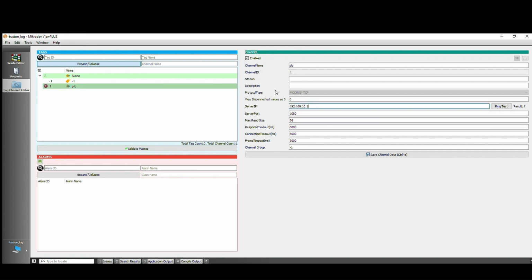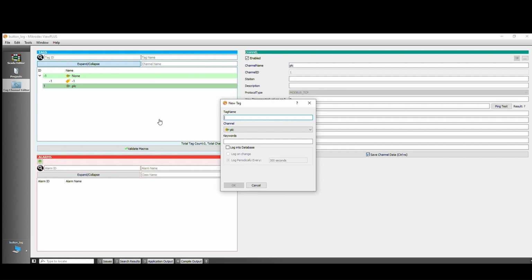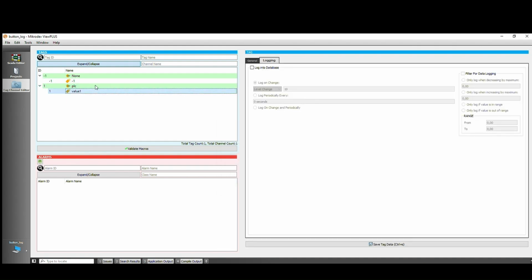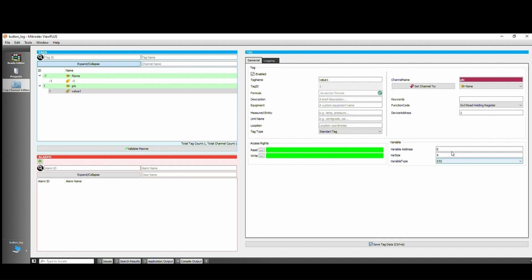Let's establish communication between SCADA and PLC and send values from the Modbus register where we will log from the PLC. After entering the PLC IP and port information, let's check and enter the register address we will read from the PLC into our SCADA. When the button is pressed, we want to log the received values.